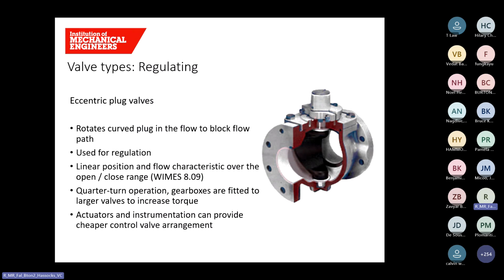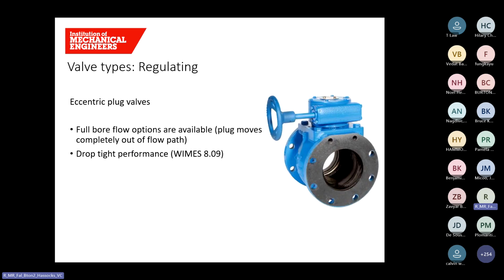So if you've got a particular flow or pressure set point you need to achieve, you can set the valve up to modulate to achieve those set point pressure or flow requirements. There is also a full bore version of the eccentric plug valve, meaning the disc moves entirely out of the flow path. Eccentric plug valves are also drop tight, meaning they can also be used for isolation.